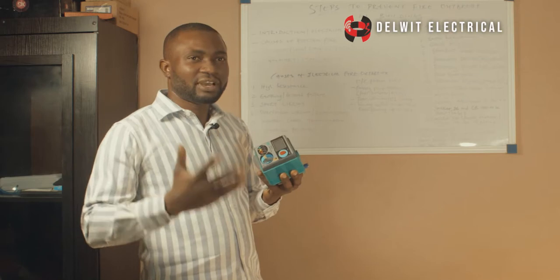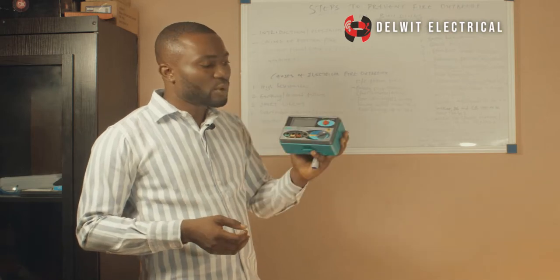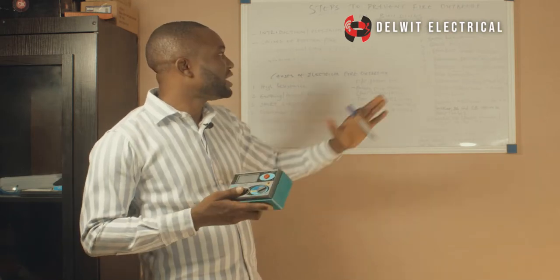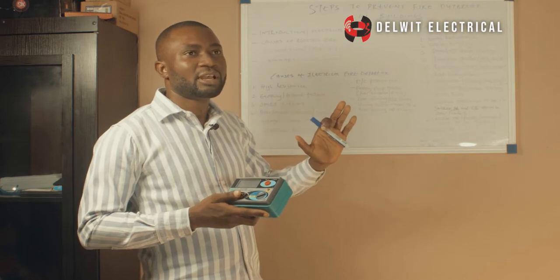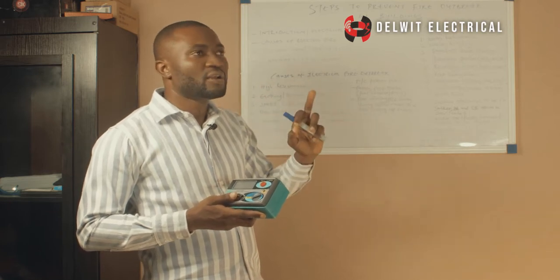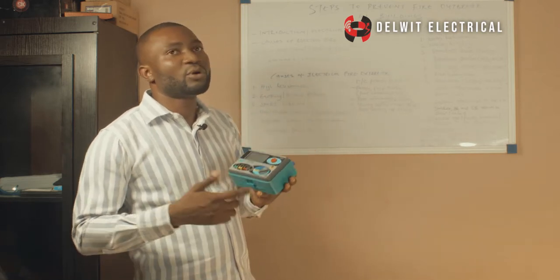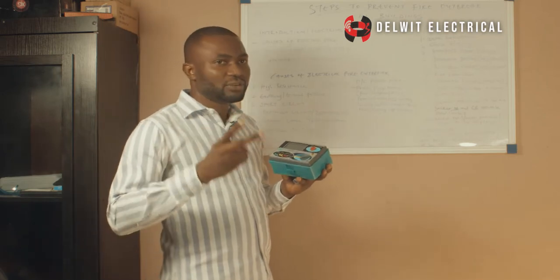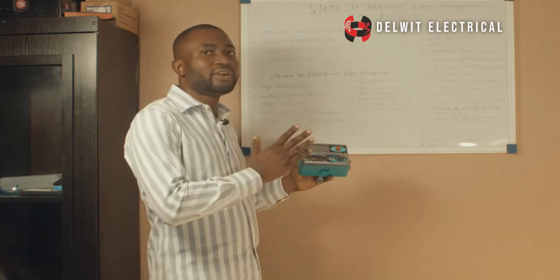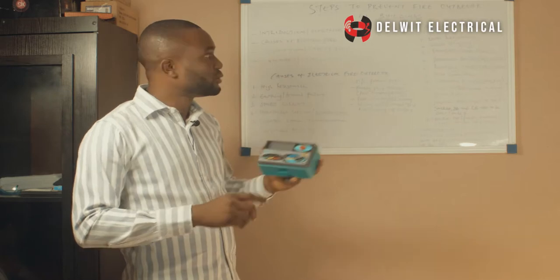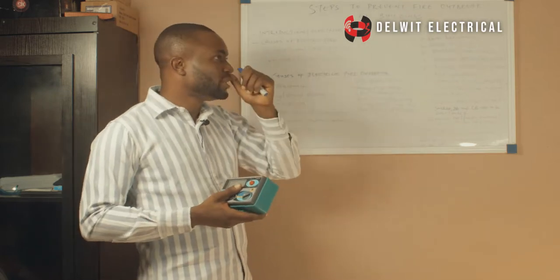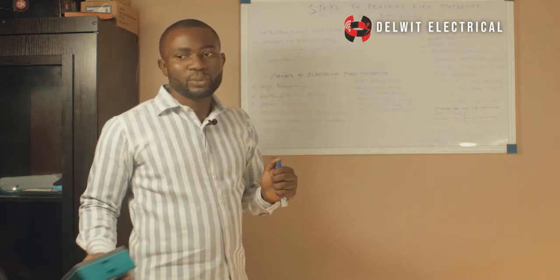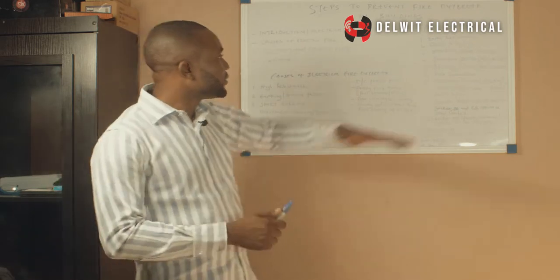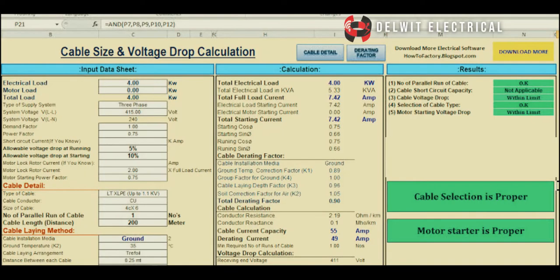If not, I advise you call a competent electrical engineer that will come with this equipment to measure the earth resistance. It's very important. You should do it at least once a year for residential buildings. Then for commercial buildings, I advise you carry out your test twice a year, one in the rainy season, one in the dry season, to ensure that your resistance is still within the required ohmage that is needed. The second one is cable sizing. Cable sizing also is quite necessary.